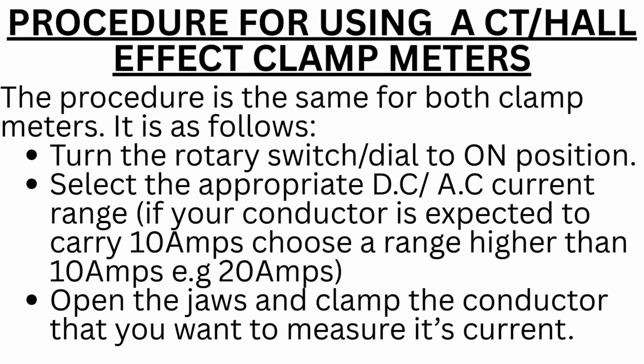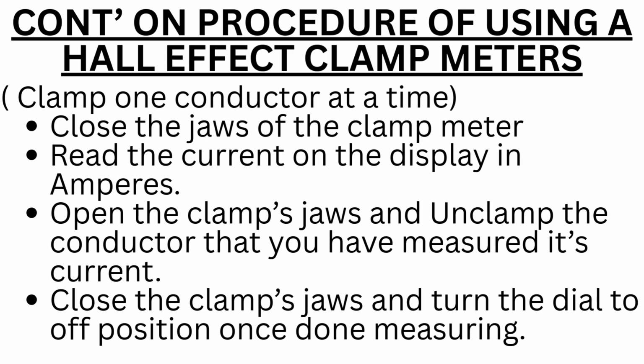Procedure for using a CT or Hall effect clamp meter. The procedure is the same for both clamp meters. It is as follows. Turn the rotary switch or dial to the on position. Select the appropriate DC or AC current range, that is, if your conductor is expected to carry 10 amperes, choose a range higher than 10 amperes, for example 20 amperes. Open the clamp's jaws and clamp the conductor whose current you want to measure. Note: clamp one conductor at a time. Close the jaws of the clamp meter. Read the current on the display in amperes. Open the clamp's jaws and unclamp the conductor that you have measured. Close the clamp's jaws and turn the dial to the off position once done measuring.